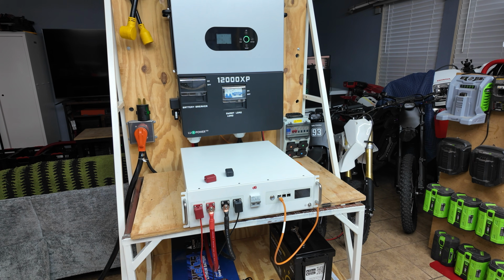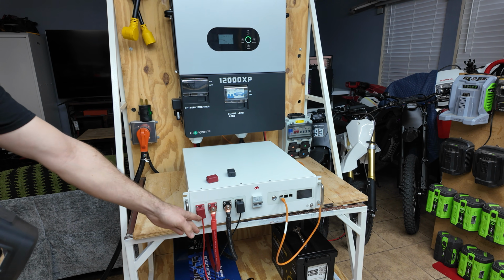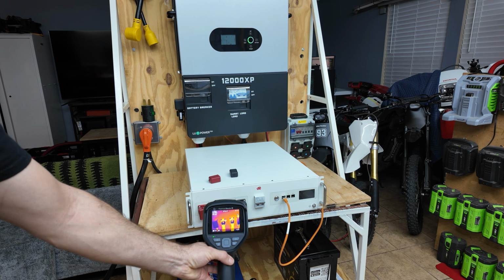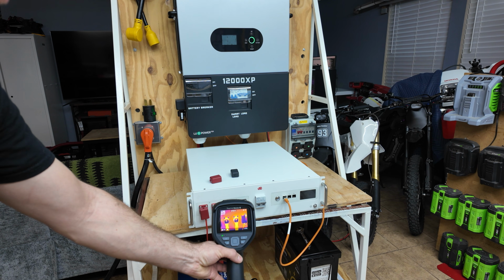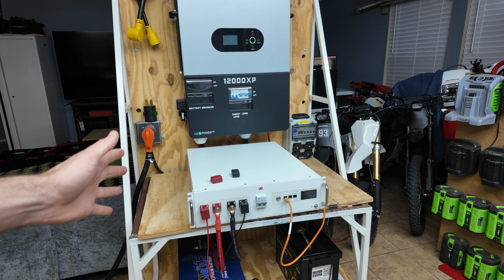Now some of y'all might be curious about these terminals running at 100 amps because they're a little bit small, so I went ahead and pulled the thermal camera out. The hottest part of the terminal is 94 degrees, so definitely not anywhere near danger temperatures.